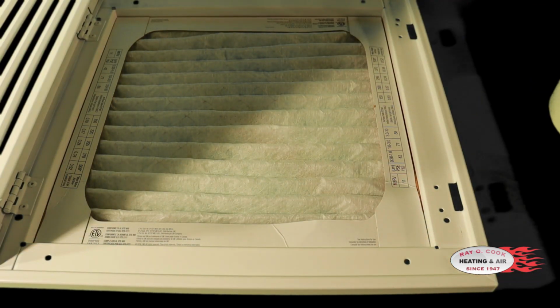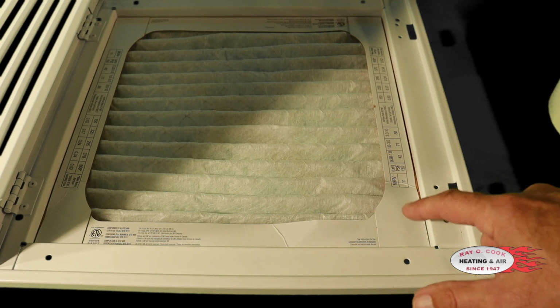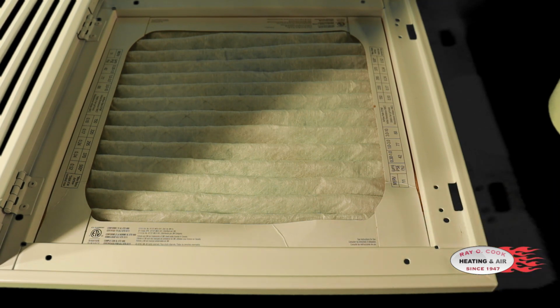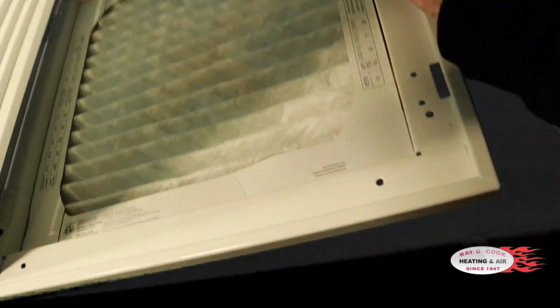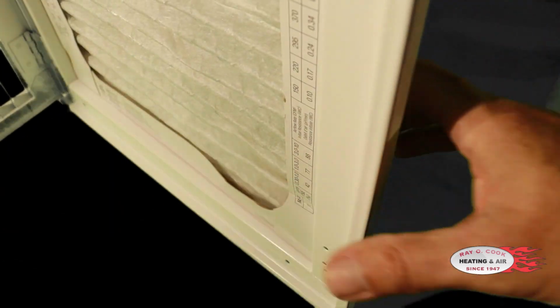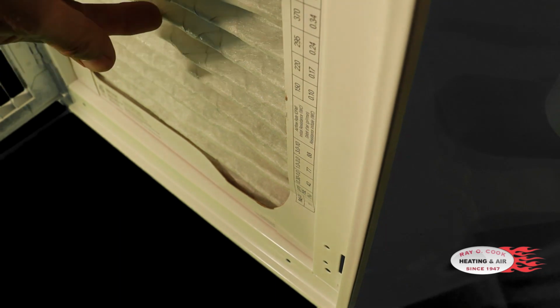So the unintended consequences of the wrong filter with the wrong pressure drop go well above just starving the equipment for air. We have other issues with the equipment as well. So when you let air bypass the filter, on the other side of this is going to be the duct that goes to the unit. So when we look at this filter here on our ceiling and the air is going in here, okay, on the other side we're going to have a duct connected to it all the way to the unit.